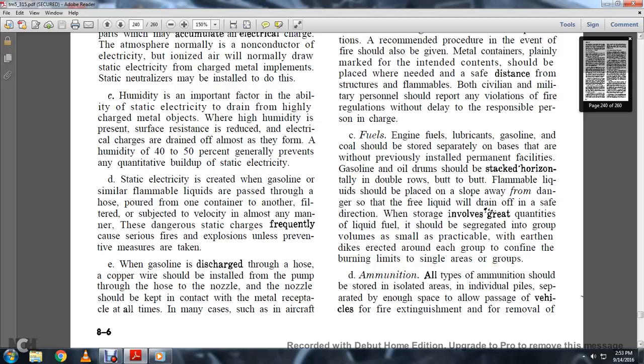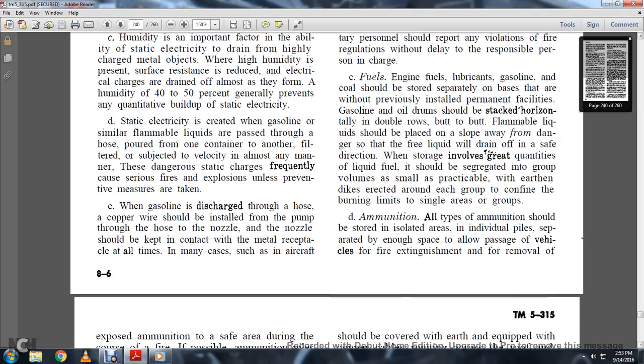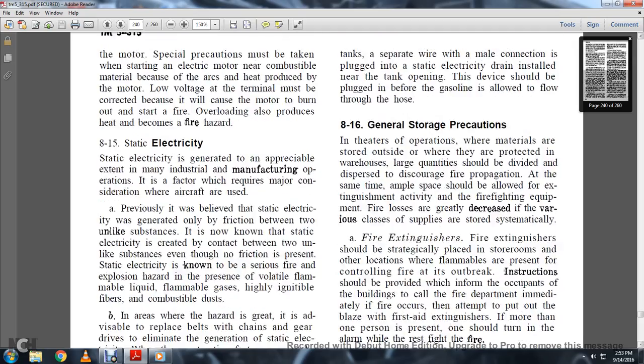These dangerous static charges frequently cause a series of fires and explosions unless preventive measures have been taken. When gasoline is discharged from the hose, copper wires should be installed from the pump through the hose to the nozzle. The nozzle should be kept in contact with the metal receptacle at all times. In many cases, such as an aircraft tank, a separate wire with a male connection is plugged into the static electricity drain installed near the tank opening. The device should be plugged in before the gasoline is allowed to flow through the hose.